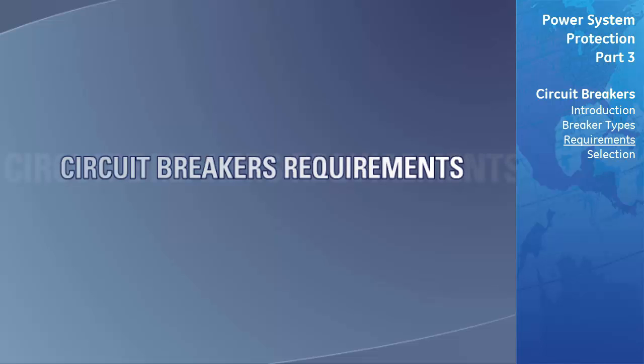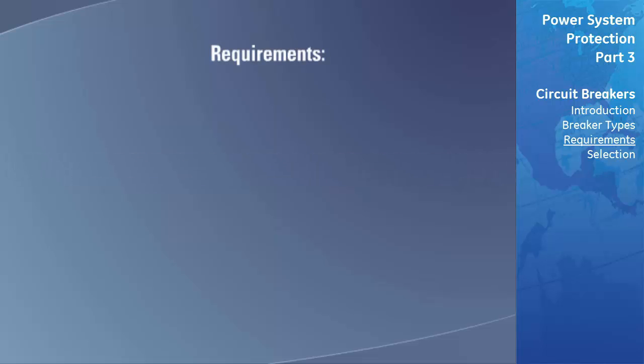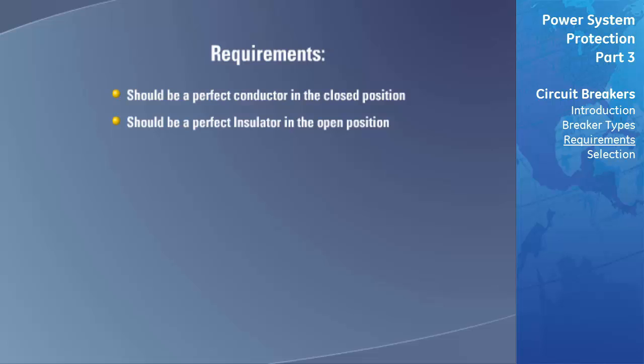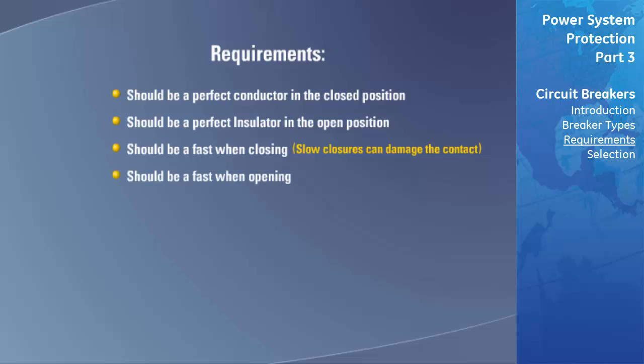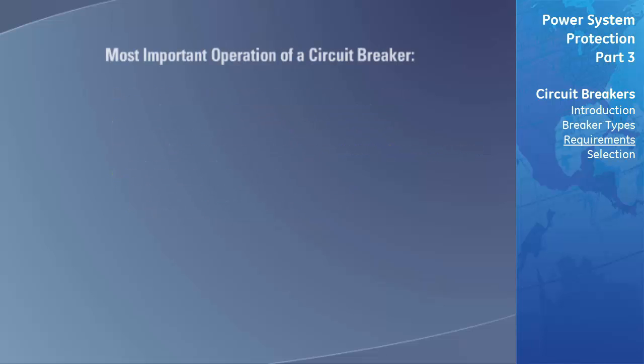The requirements for a circuit breaker are as follows: it should be a perfect conductor in the closed position, a perfect insulator in the open position, fast when closing — since current starts flowing before the contacts touch and slow closures can damage them — and fast when opening, but it must not extinguish the current before its zero crossing and must not produce overvoltages.